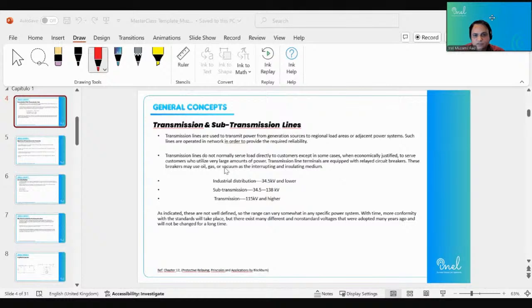As far as IEEE and IEC standards are considered, if it is 34.5 kV and lower, then it is considered an industrial distribution network. But if it is between 34.5 kV and 138 kV, then we can say this is the sub-transmission level. And if it is above 115 kV, then sometimes we call it the transmission level. As you can see, 138 kV is considered sub-transmission, but at the same time, 115 kV is considered a transmission line. So there is no clear-cut boundary between transmission and sub-transmission lines. We may consider transmission and sub-transmission as one entity, and distribution, which is up to the 34.5 kV level, as the distribution level. So this is the classification of the transmission lines.